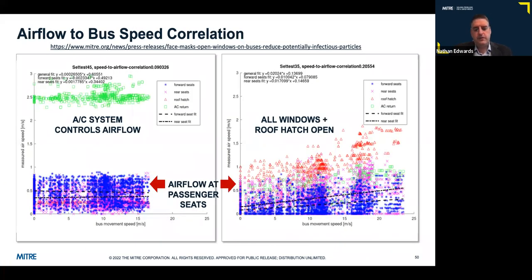Some of the other data we looked at used our 16 anemometers throughout the bus. In the graph on the left, we closed the bus and ran the HVAC system alone, and we also inserted MERV 13 air filters in the back system. What you notice is a pretty linear effect with the airflow in all the passenger seats compared to what's right at the rear register of the HVAC system. That HVAC, at 2,200 cubic feet a minute, essentially creates a flow system from front to back, so eventually it would capture all the particles. When we did not have the MERV 13 filter in place, the airflow would be similar, but the particles would reach a well-mixed environment much, much faster. This really emphasized the importance of having good filters in the back to trap those particles and reduce the risk.